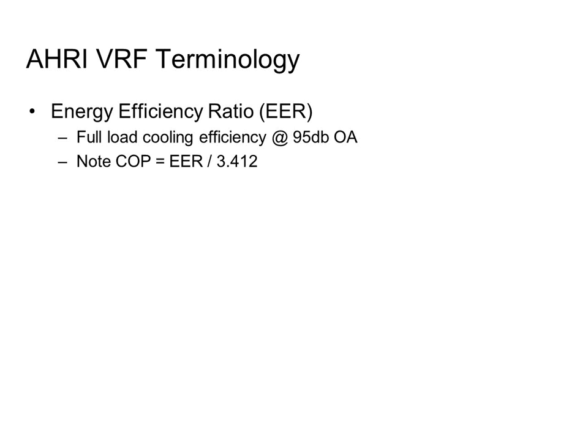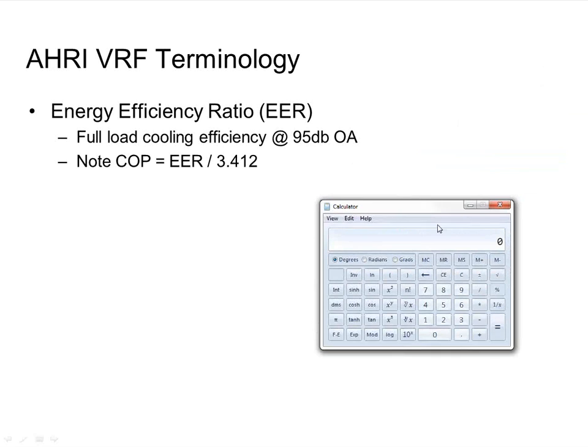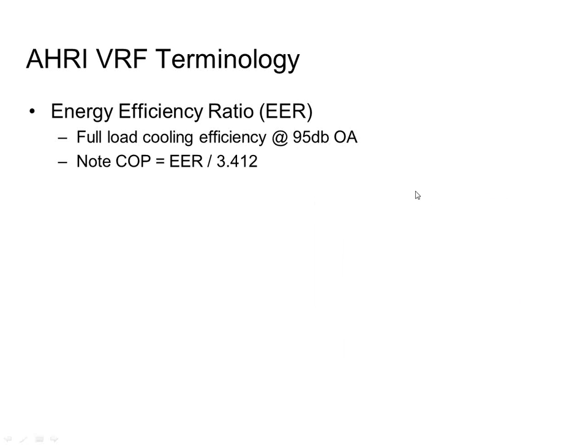You can convert COP and EER directly because they're both steady state scenarios. If you take the EER and divide it by 3.4, you'll get the COP, right? So for sake of argument, if I had something that had an EER of 12, I could take 12 divided by 3.412, and if I did it right, my COP would be 3.5, which would be 351% efficient in this case.